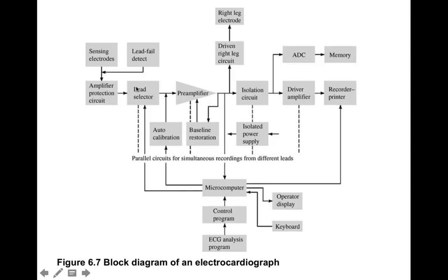There is a lead selector, and typically you will have parallel circuitry that does a simultaneous recording from different leads. If you're an electrical engineer and have that background, you know that at some time you need to do your A to D conversion. And a lot of times that is actually done at or near this stage, as opposed to how it's shown in the figure. And then your sampling is done across, multiplexed across different channels.